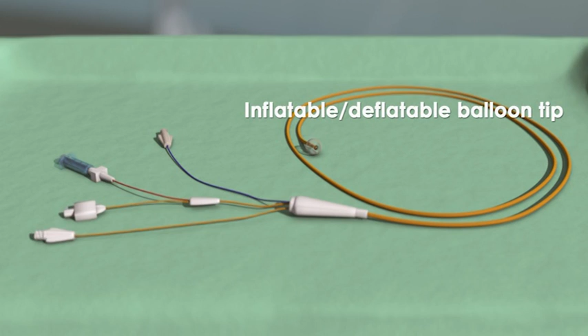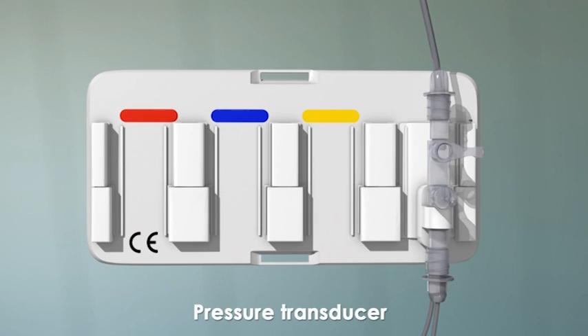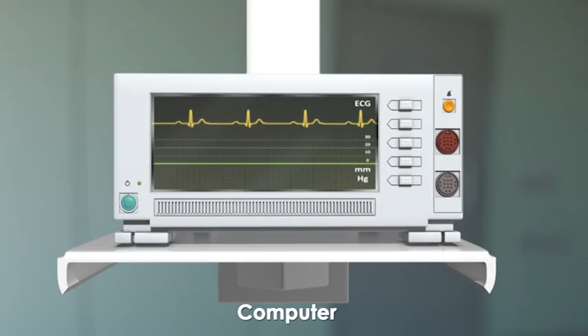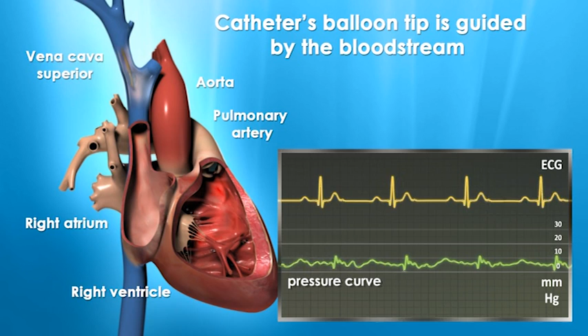A right heart catheter consists of a catheter with several different lumens, an inflatable-deflatable balloon tip for flow direction, a thermistor, a pressure transducer, and a computer for measuring and displaying obtained data. One function of the balloon at the tip is to guide the catheter to its desired destination. After the balloon has been inflated, it is taken up by the venous bloodstream and flow directed to and subsequently through the right side of the heart. On its way through the heart to the pulmonary artery, it measures pressure in the right atrium, the right ventricle, and the pulmonary artery itself. Additional hemodynamic parameters can be calculated from these direct invasive measurements taken with the catheter.